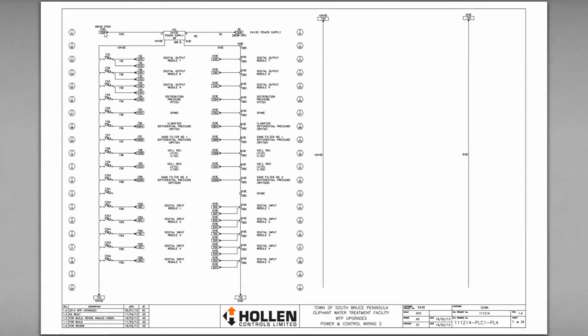So you can see here on this page, we have a 24-volt power supply. It's receiving 120 volts, and then coming out of it is 24 volts DC, similar to a transformer where you've got one type of power coming in and a different one leaving. But switching from AC to DC is a different process electrically. Everything here is now 24 volts DC.